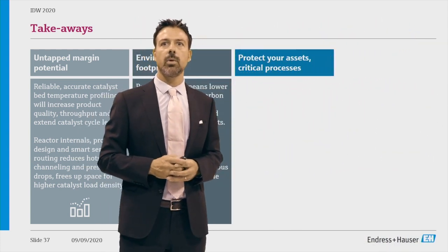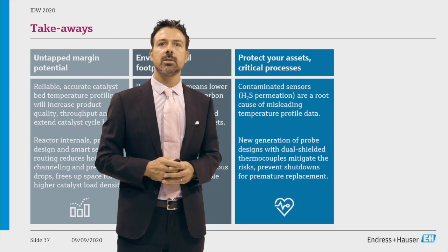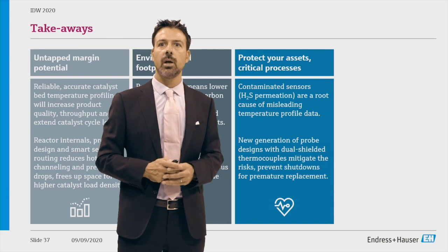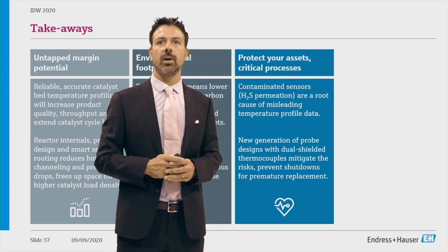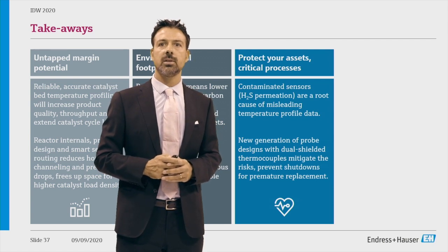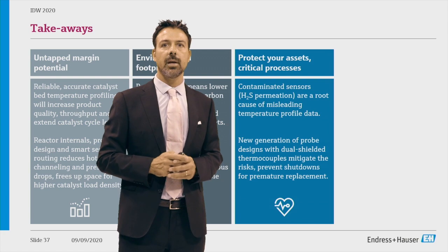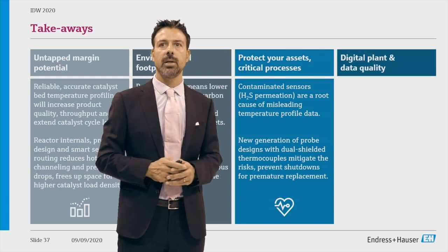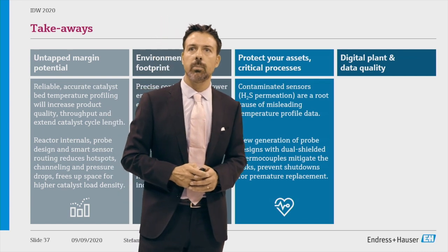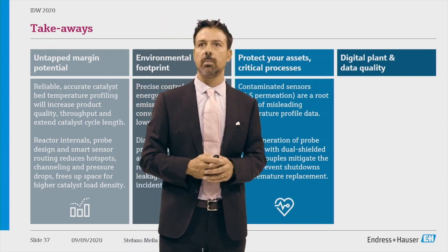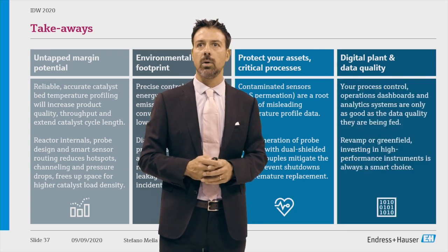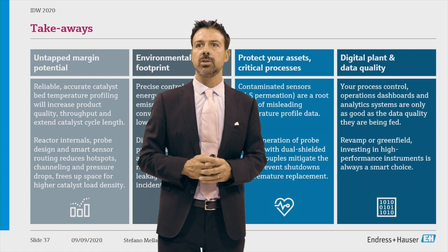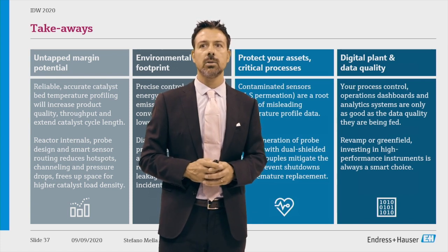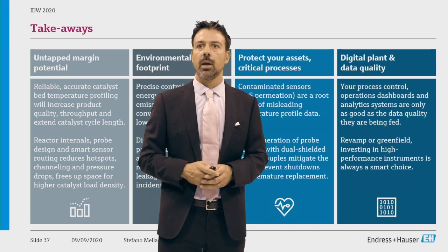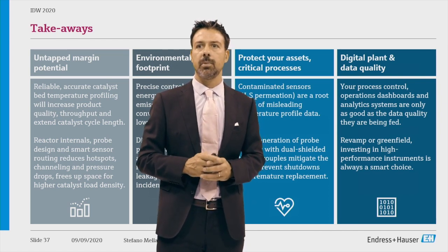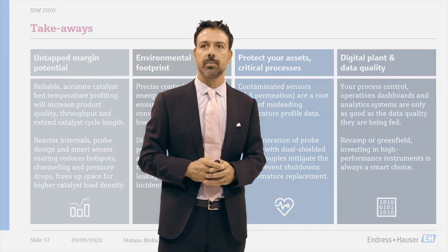About protecting your assets and critical processes, contaminated sensors, for example, because of H2S permeation, are root cause of misleading temperature profiling data. New generation of probe designs with dual shield thermocouples mitigate the risks, prevent shutdowns for premature replacement. And we all know how important is the digitalization, so to have digital plants and to have high data quality. So your process control, operations dashboards, and analytics systems are only as good as the data quality they are being fed. Revamp or greenfield, investing in high performance instruments is always a smart choice.